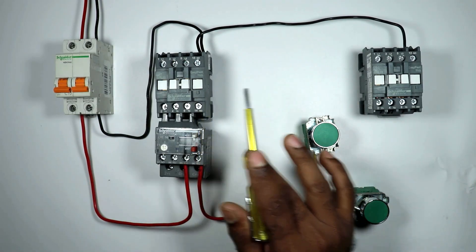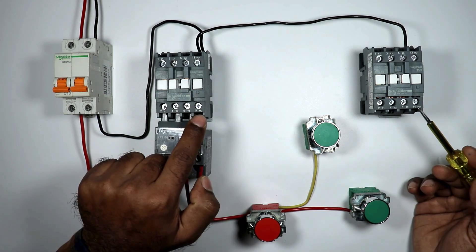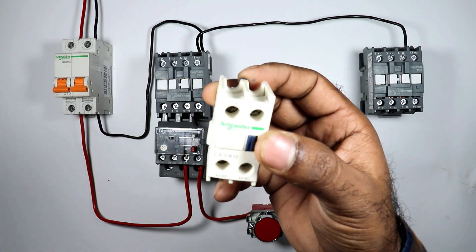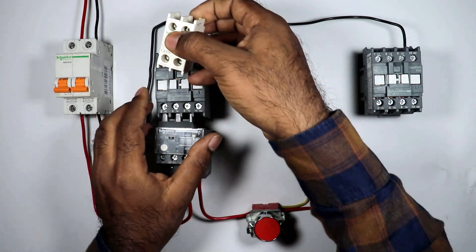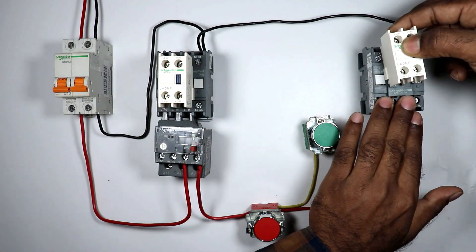These contactors have no NC contact — only NO contact is there. This is why I'm using an add-on block here. In this add-on block, here is the NO contact and here is the NC contact. We will use this NC contact for interlocking. I'm connecting this add-on block with this contactor, and in the reverse contactor also we will connect an add-on block.